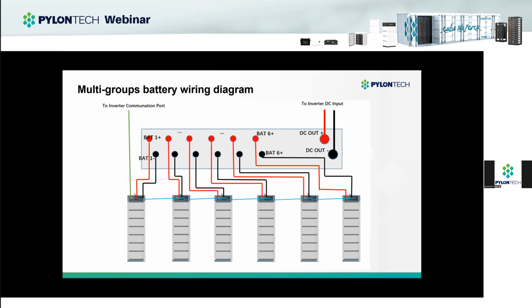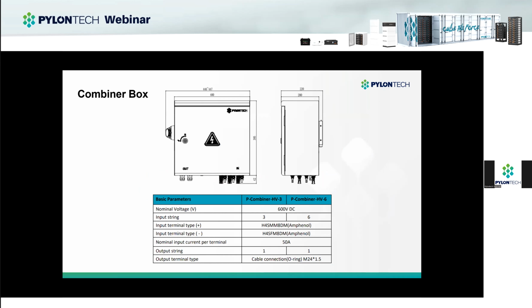And we connect them to the inverters through a combiner box. So you're going to have a DC combiner box between the H1 batteries and the inverters. But if you just have one stack, then you don't need this device. If you have more than one, or if the current is huge, then you're going to have this. So this is the combiner box.